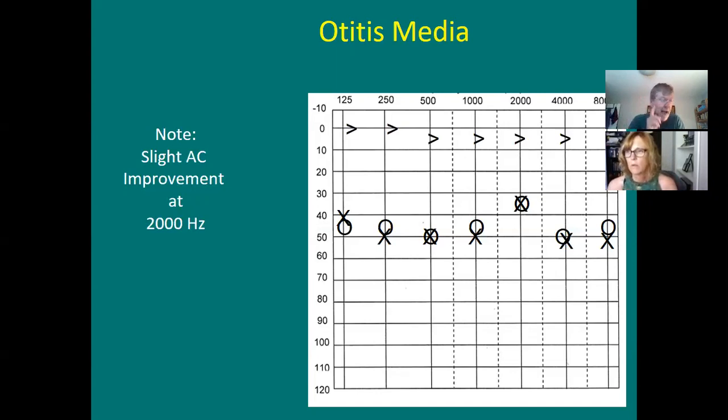But just realize collapsed ear canals during hearing testing with circumaural headphones can result in a high-frequency conductive air bone gap, highly unlikely due to natural causes. So if it collapses during the hearing test, will it reopen? Yeah. Will it correct itself eventually? Or no, not really. Not as long as you're wearing the headphone, it'll be collapsed, and then you take off the headphone. Headphone off, it will open back up. Yeah. Oh, okay. And the solution for that person is to use insert headphones. You bet. I was never sure if it stayed collapsed. No, it doesn't.